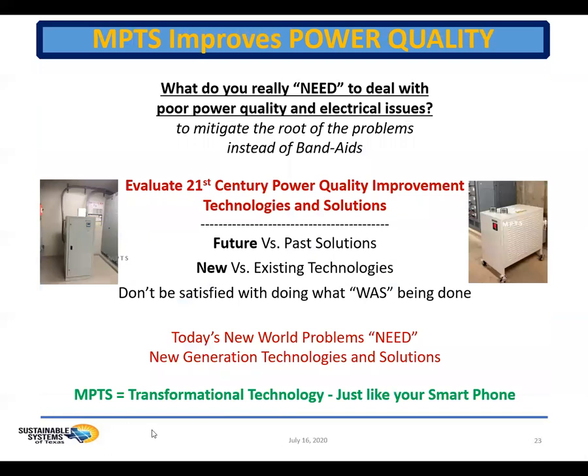So MPTS improves power quality. It's about using a 21st century solution versus using solutions from previous centuries. It's future solutions versus past solutions. A frequently used past solution is capacitor banks. Capacitors correct the power factor. They do not improve or eliminate harmonics. Capacitors actually add to total harmonic distortion.